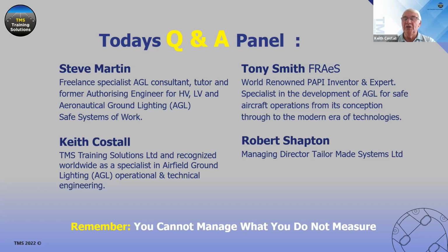There are time constants in the design of the IEC standard, 61822, on the changeover. We can't go into the detail, but there is a time constant associated with the transition between steps, and the time constant associated with the stability of the steps. So you're going from 6.6 down to 5.2, for example, and there is a time frame associated with the stability. That's in IEC 61822, which is the design specification for CCRs.